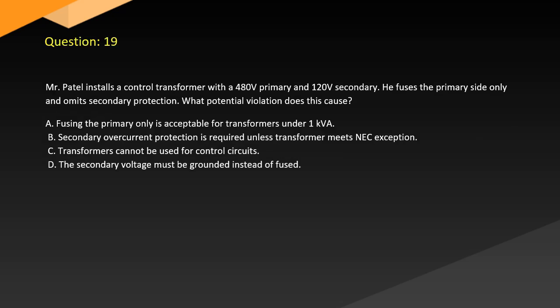Question 19. Mr. Patel installs a control transformer with a 480 volt primary and 120 volt secondary. He fuses the primary side only and omits secondary protection. What potential violation does this cause? A. Fusing the primary only is acceptable for transformers under 1 kVA. B. Secondary overcurrent protection is required unless the transformer meets an NEC exception. C. Transformers cannot be used for control circuits. D. The secondary voltage must be grounded instead of fused.